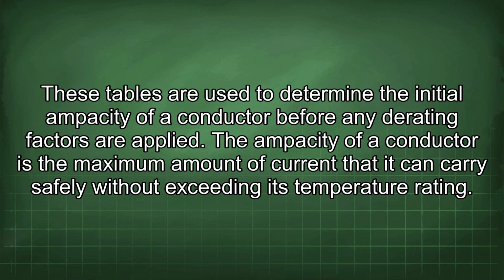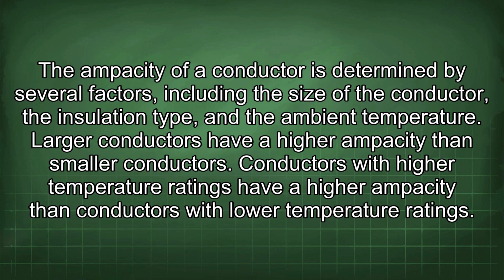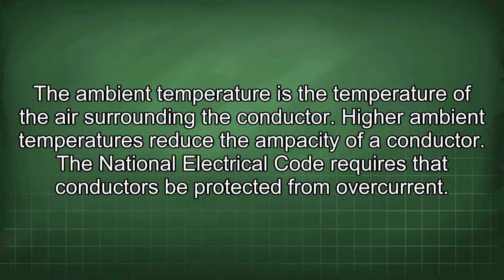The ampacity of a conductor is the maximum amount of current that it can carry safely without exceeding its temperature rating. The ampacity of a conductor is determined by several factors, including the size of the conductor, the insulation type, and the ambient temperature. Larger conductors have a higher ampacity than smaller conductors. Conductors with higher temperature ratings have a higher ampacity than conductors with lower temperature ratings. The ambient temperature is the temperature of the air surrounding the conductor. Higher ambient temperatures reduce the ampacity of a conductor.